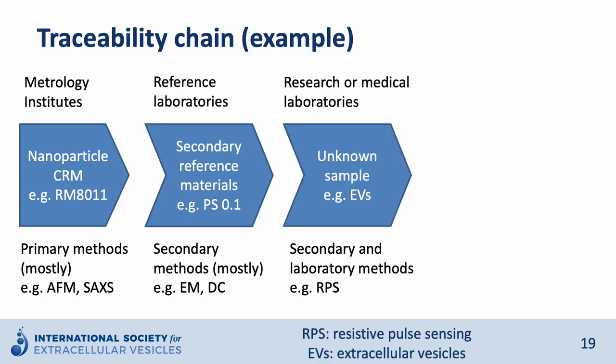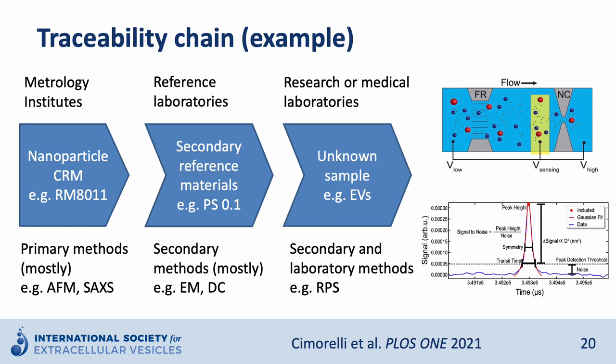On the next level we have the unknown sample, for example EVs. These measurements are performed in research or medical laboratories, usually using secondary and laboratory methods. One example is resistive pulse sensing, which is based on the Coulter principle. In RPS, particles pass through a nano constriction and cause an electric signal — a pulse — which is proportional to the volume excluded by the particles. To calibrate the pulse height to diameter, secondary reference materials made of polystyrene are usually used.